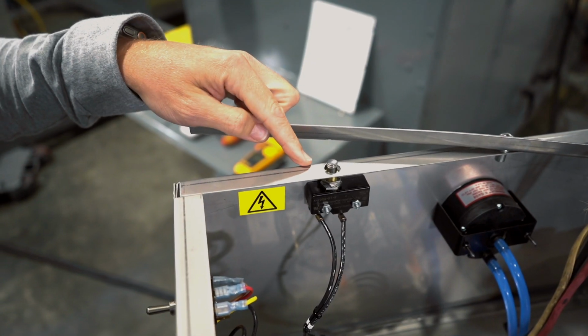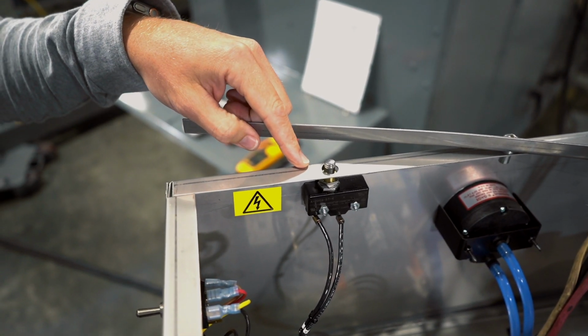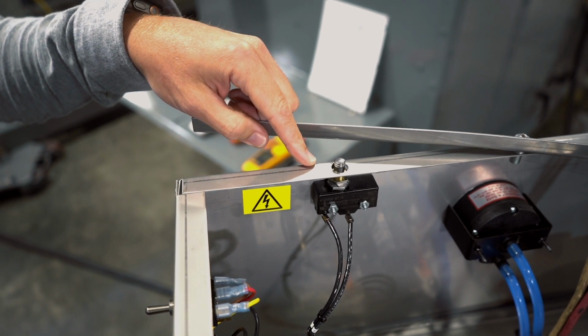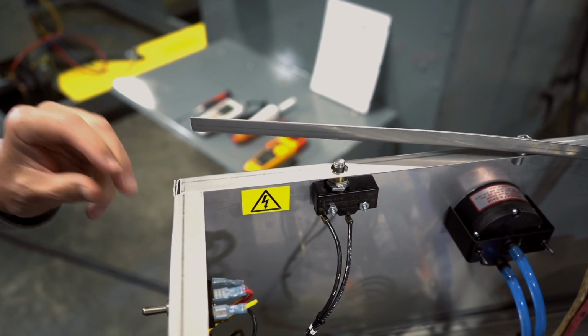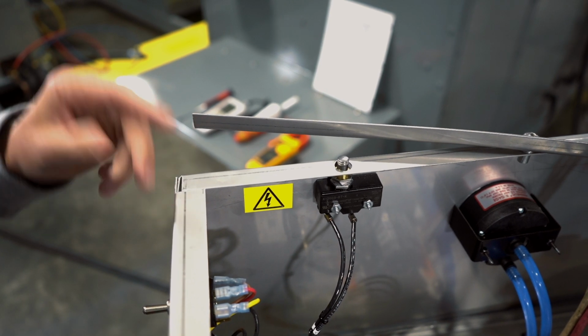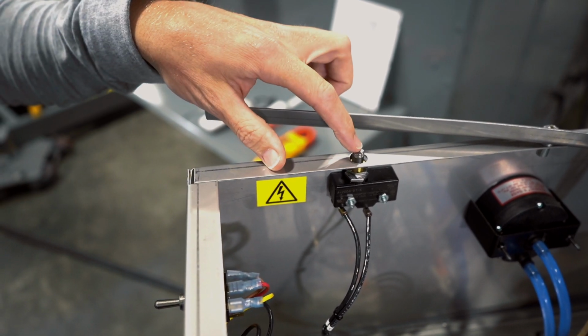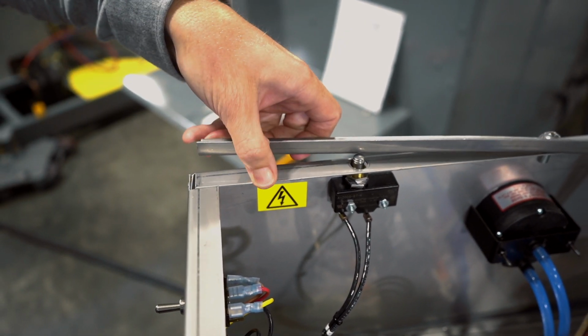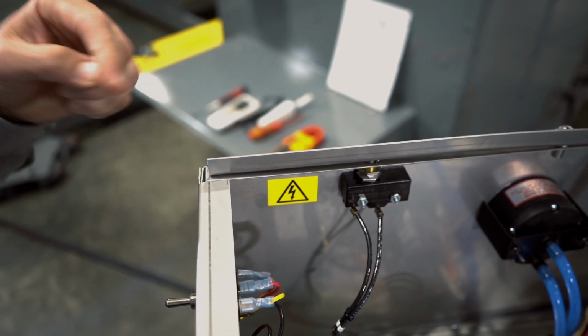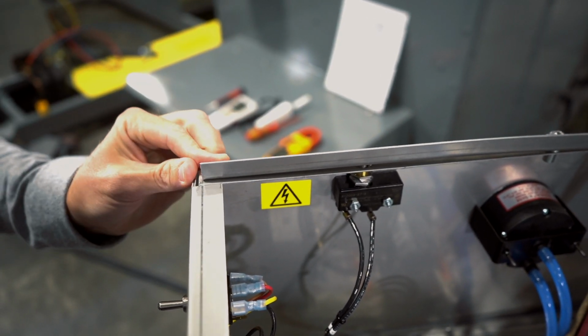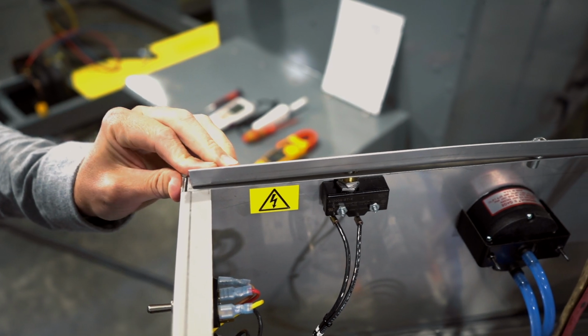This lid switch located on the top panel is designed as a safety disconnect switch to make the equipment safe in the event the top lid comes off. As the top lid is installed, this switch compresses and allows the 480 volts to go into the unit, and therefore you can operate the unit.